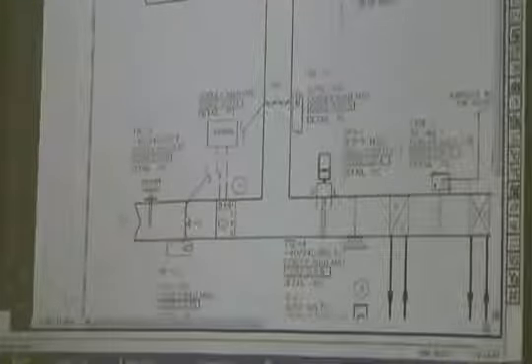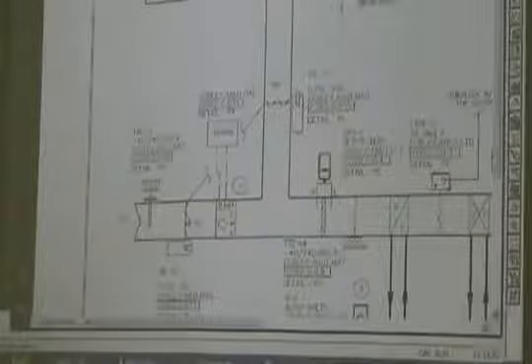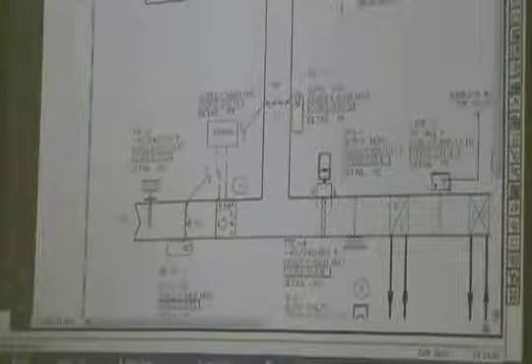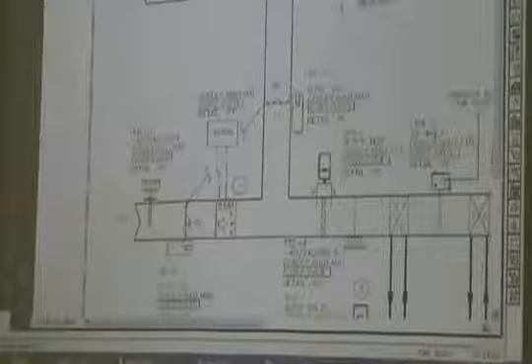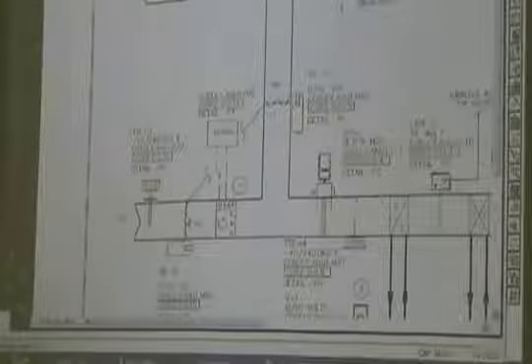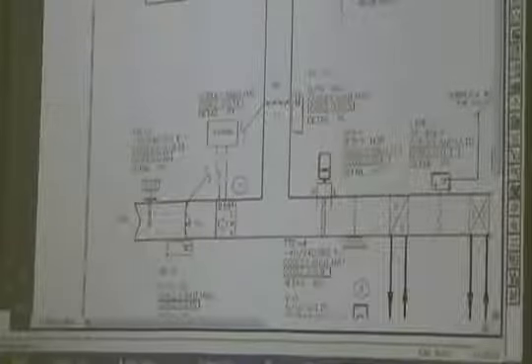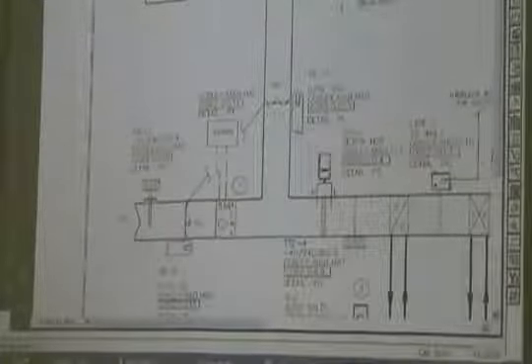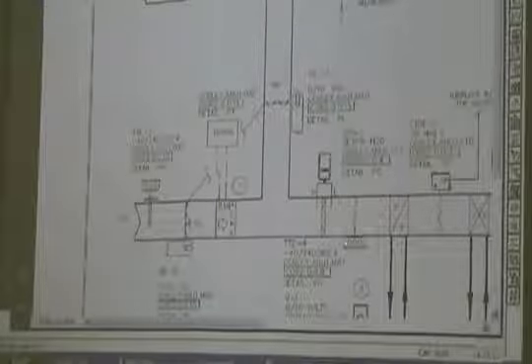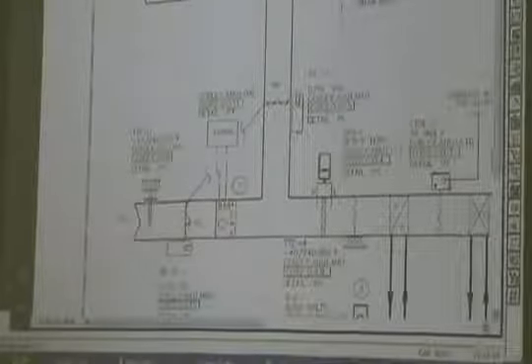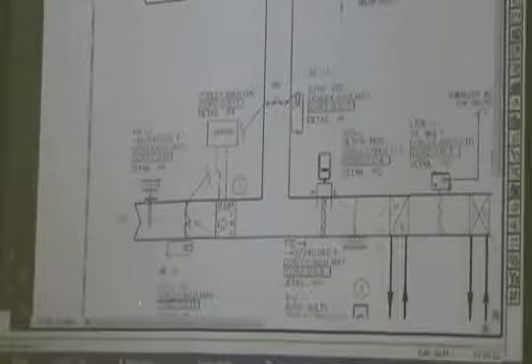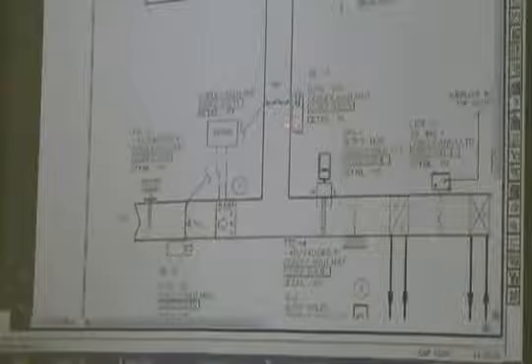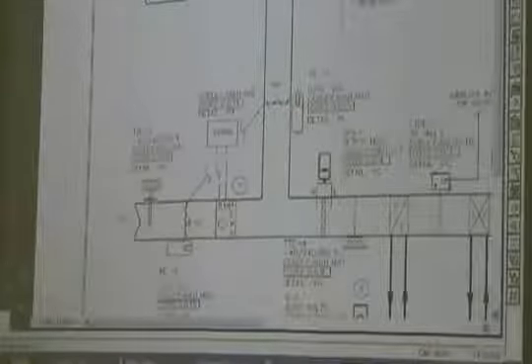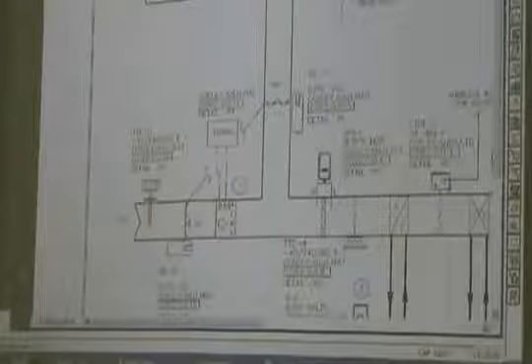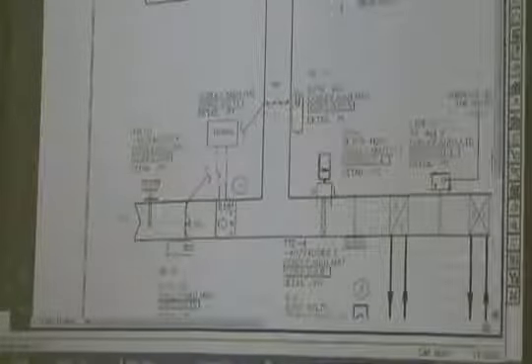So when we switch over at 72 or whatever that return air temperature is, it's probably going to go wide open. And it's not going to go below wide open until when? Freezing. So we're mixing these two streams to maintain a temperature of 55 degrees. As we start going below 55 on our outside air, then this is going to start pinching down, and that'll open up, and we'll mix those two streams to maintain the discharge air temperature. So that's our mixing dampers. And again, we have an outside airflow station.